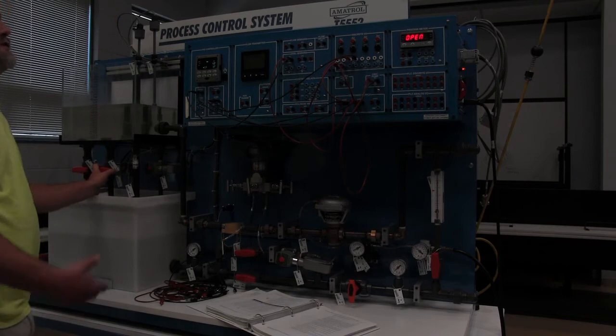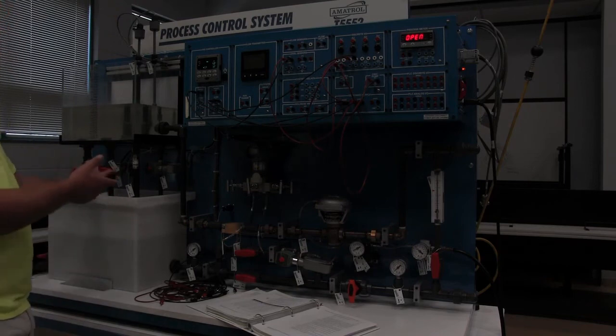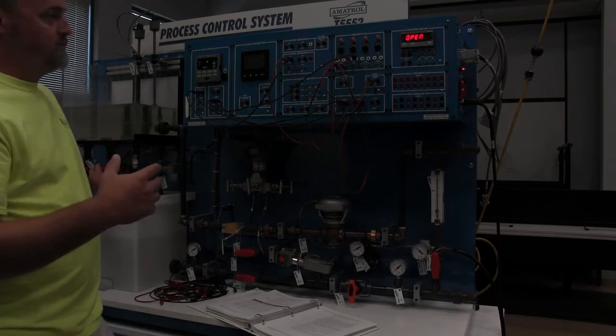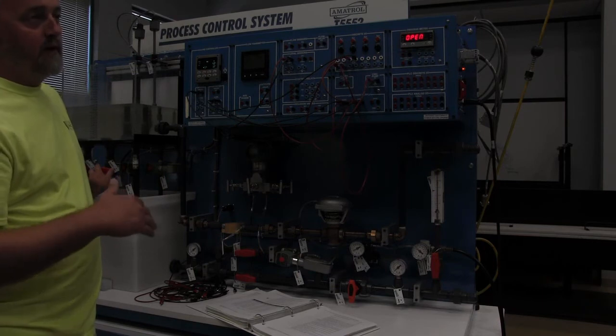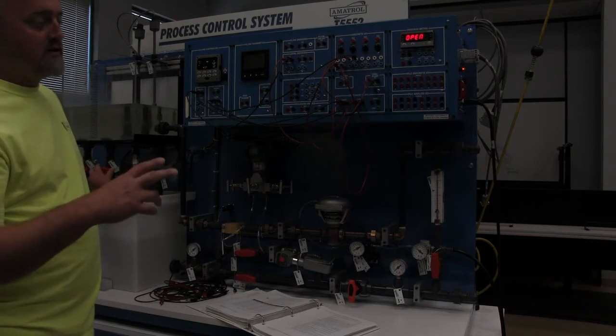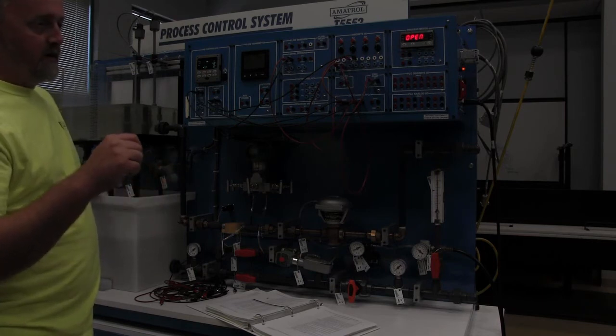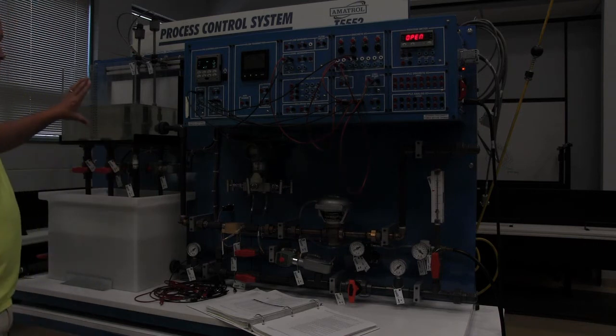So what you would do with these is, say you had your tank and you wanted to maintain a level between, and we're going to use this tank, 0 and 10. Say we never wanted to get below a 3, and we never wanted to get above an 8. We could set our low at a 3 and our high at an 8.